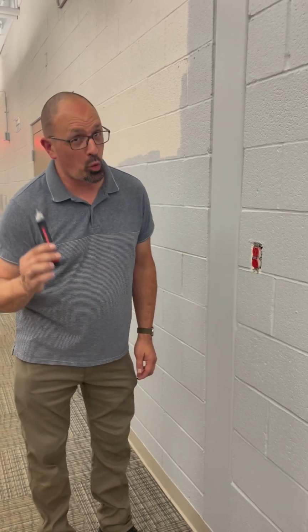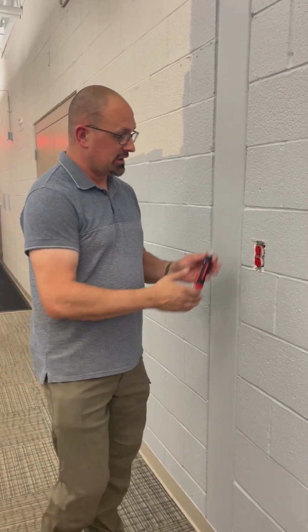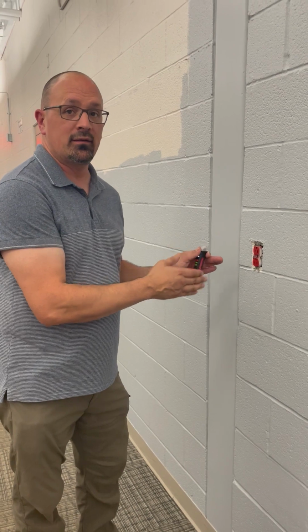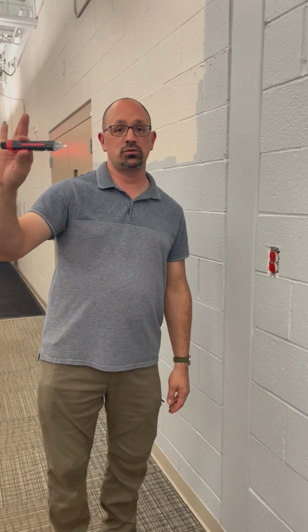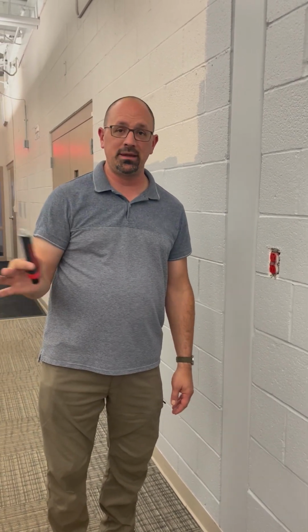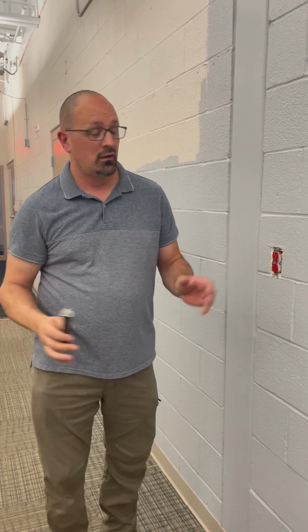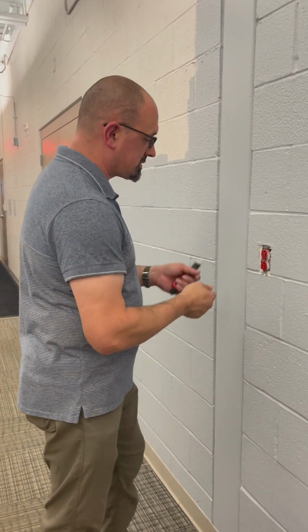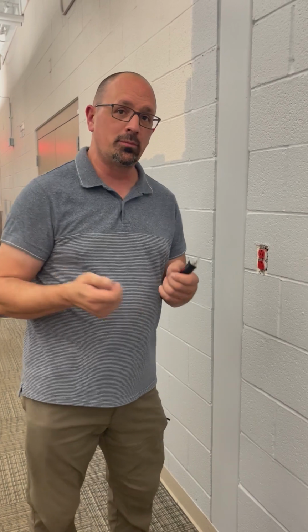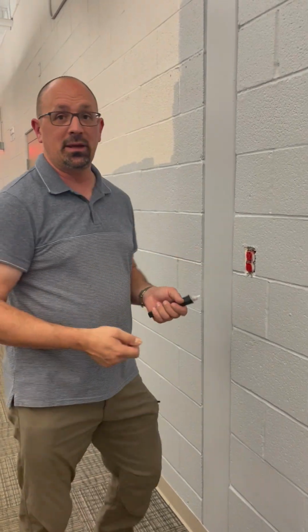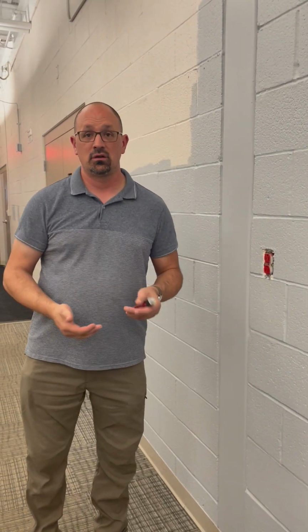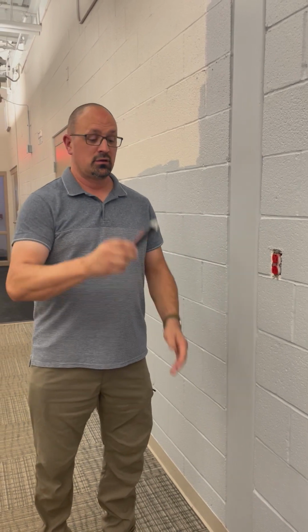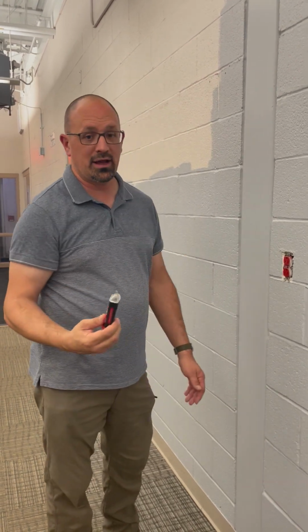If you want to be 100% certain and do it the right way, this gets you to the point, it lets you know if power might be on, maybe. The most certain way is by taking an actual electrical meter with its 2 leads, putting them in and reading the actual voltage. That will always bypass this. This will never bypass a meter. So you always really want to rely on your meter.